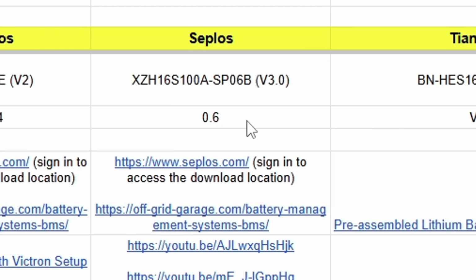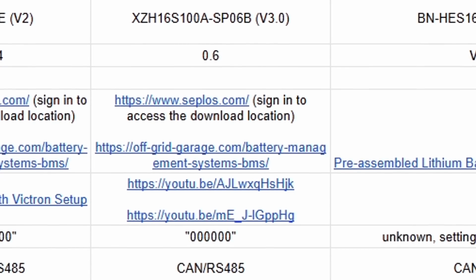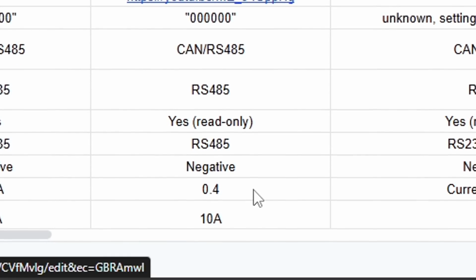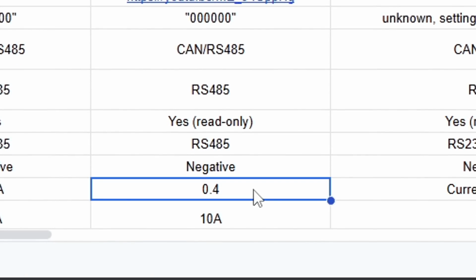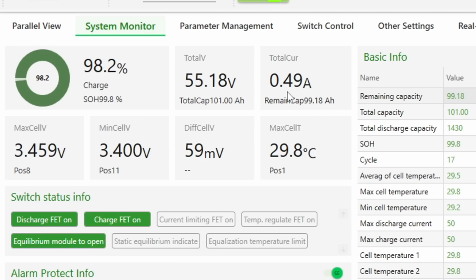Seplos. I'm just having a look at the BMS comparison spreadsheet I've made. Indication 0.4, BMS current sensitivity is 0.4 amps for this BMS. So if the current goes under 0.4, we go into standby mode. 0.40 - there we go, standby mode.